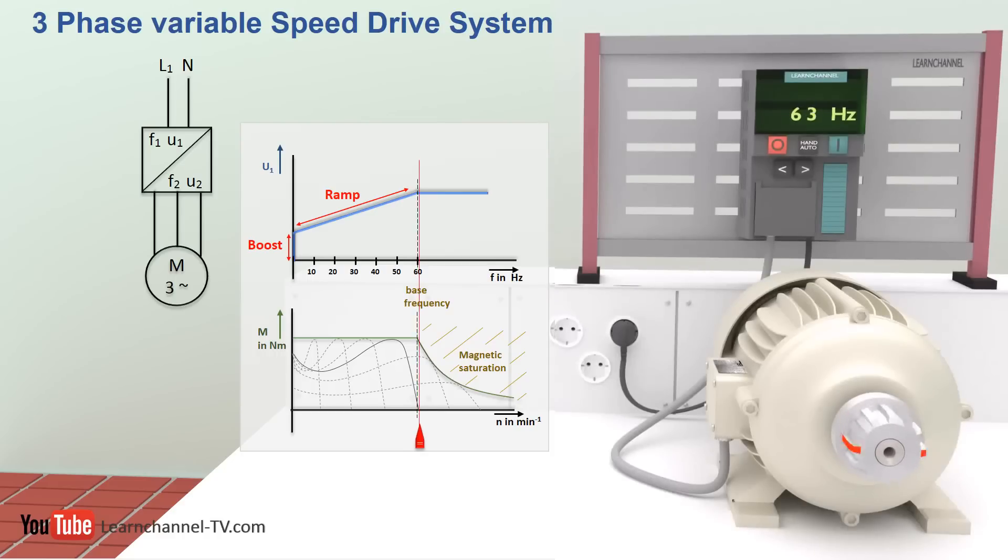The base or edge frequency is achieved when the voltage supplied to the motor reaches the mains supply voltage. Raising the frequency above the edge frequency leads to magnetic saturation which cannot be compensated anymore. As a result, the torque of the motor decreases.